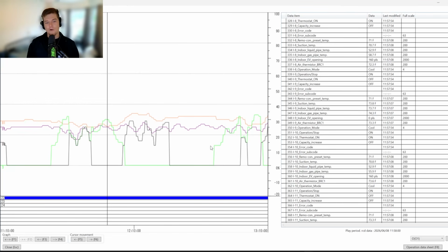And that's it. And so if I have to go in and set the saturation temperatures both on the condensing side and the evaporator side, if it's parallel operation or if it's heating operation or cooling operation, I will while I'm there. I'll change it back. But for the most part, you need to understand how the settings are set and applied to understand that maybe the data that you do record is 89 hours, but it could all be garbage. And I hate to be that guy to tell you that, but it can be. So these are all things you need to think about.